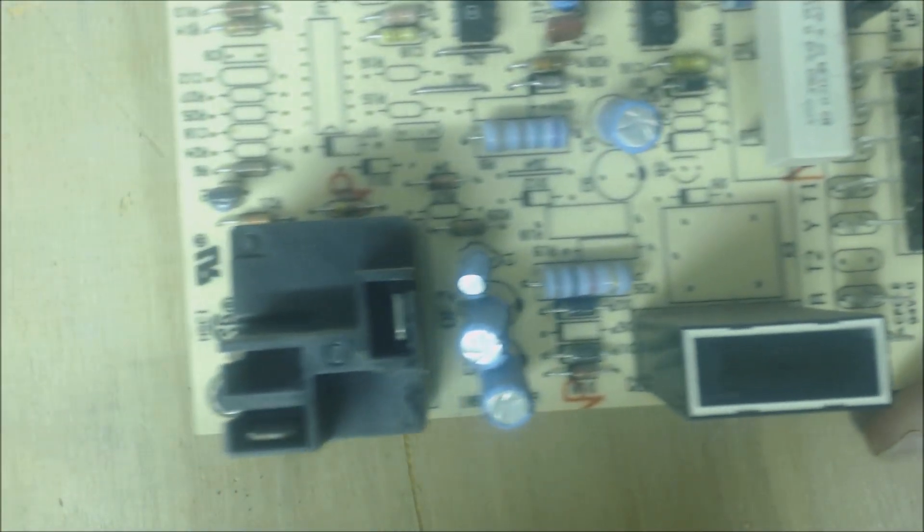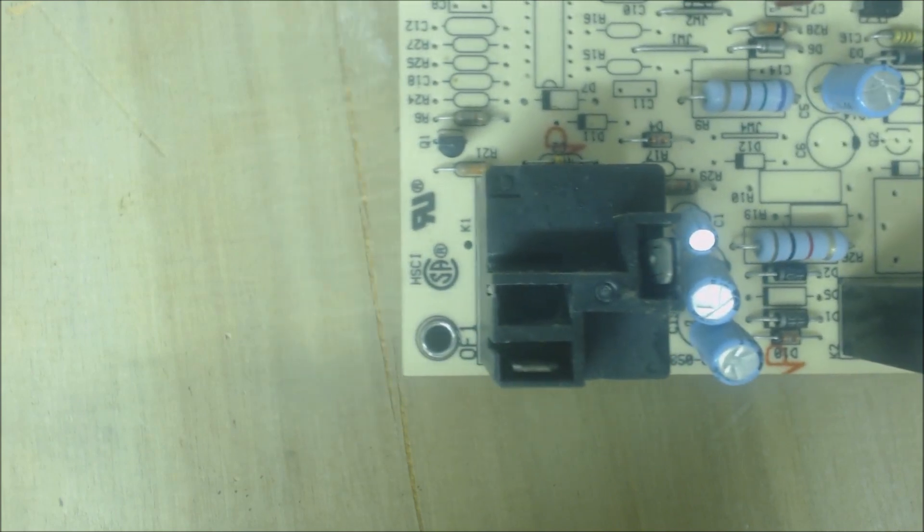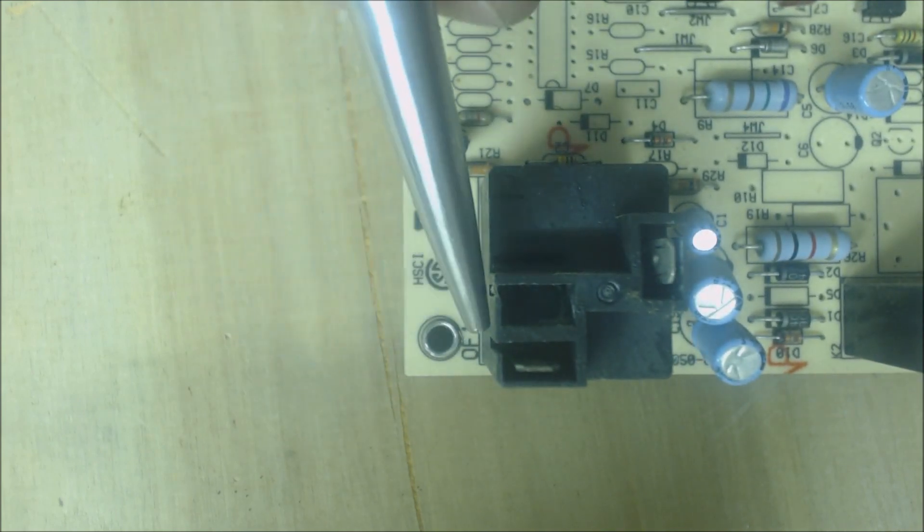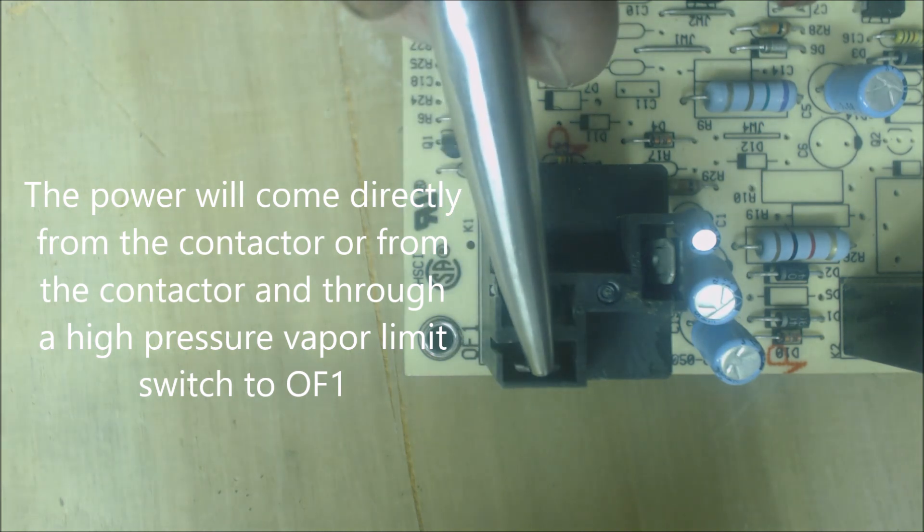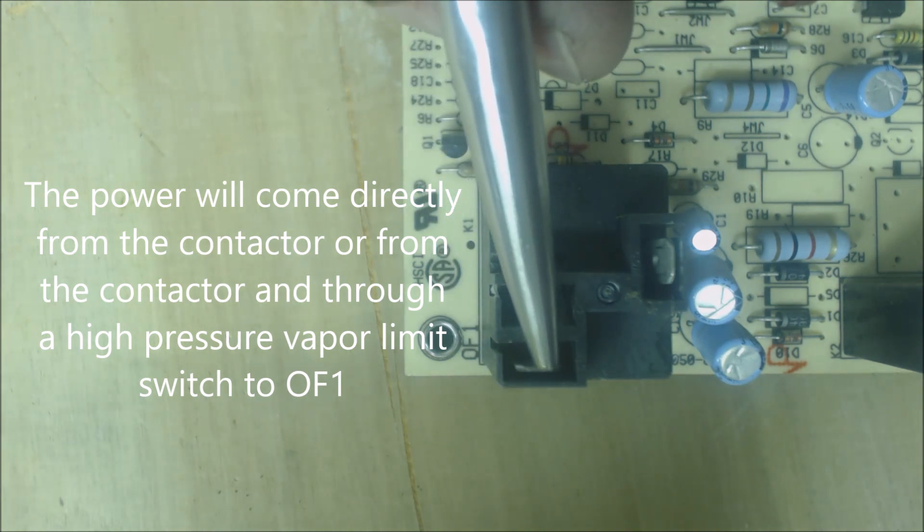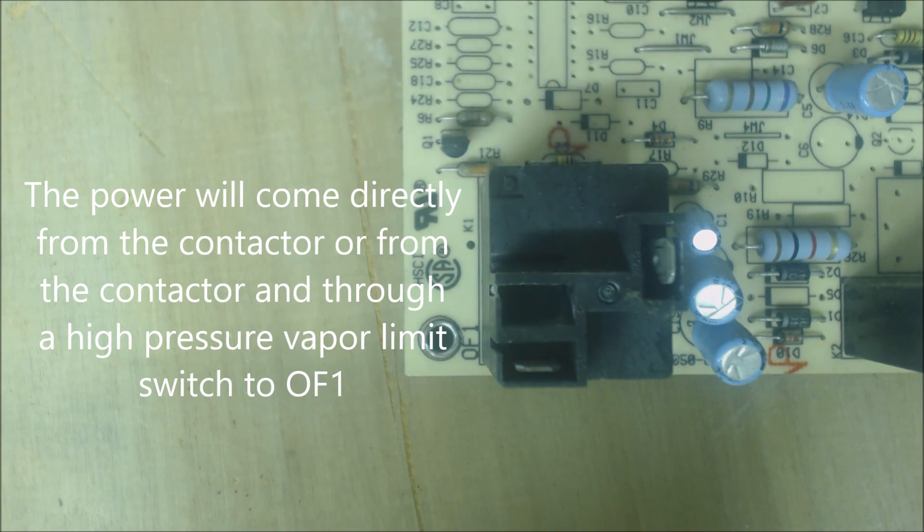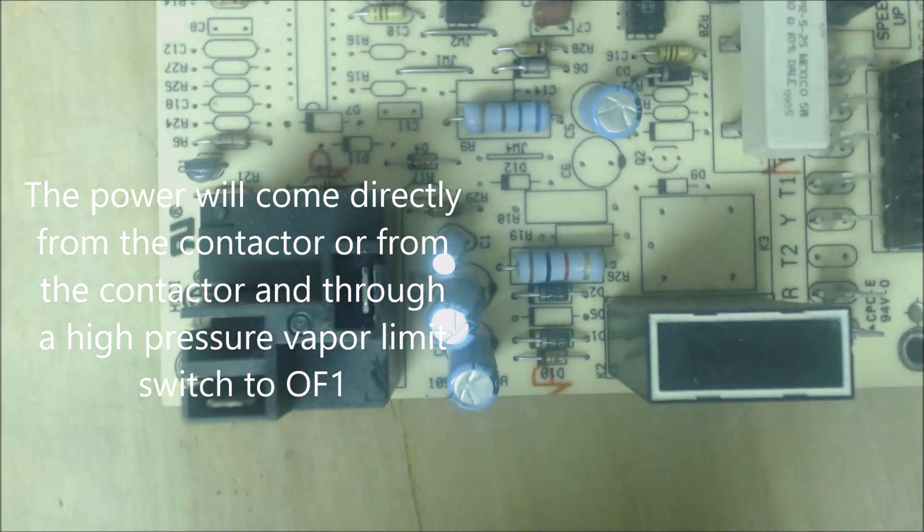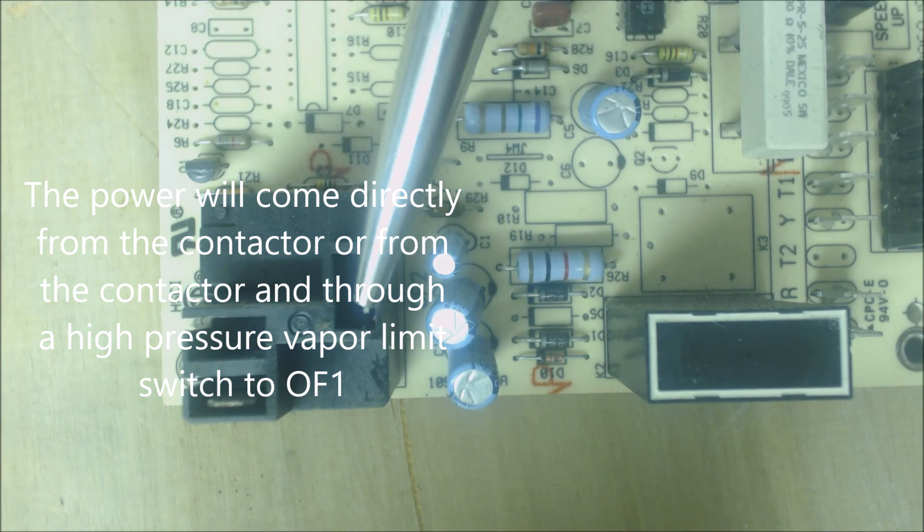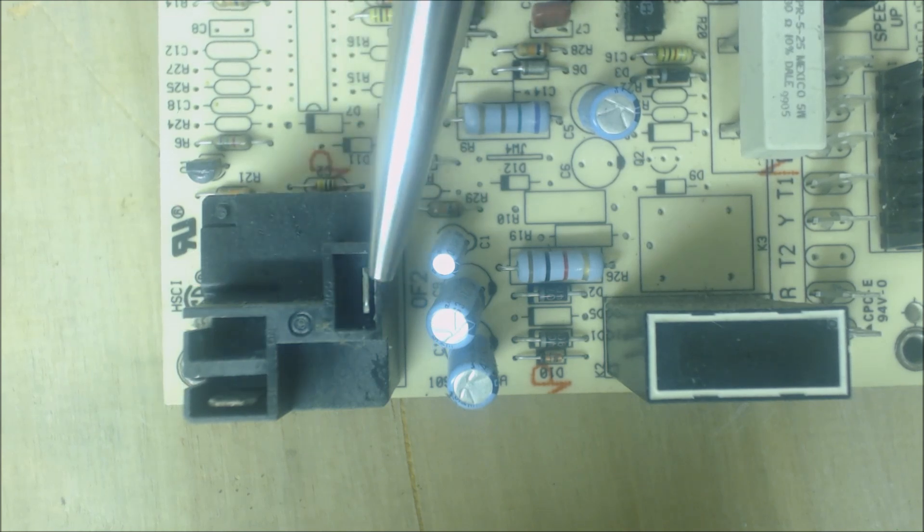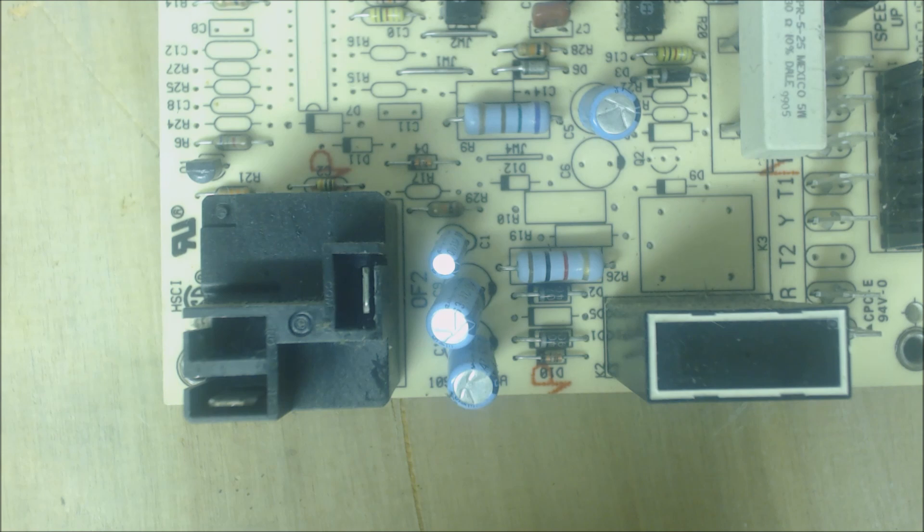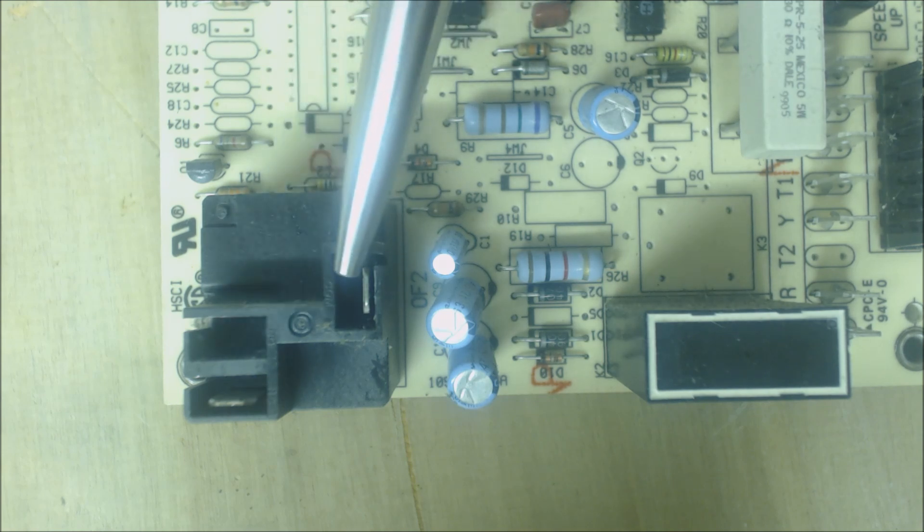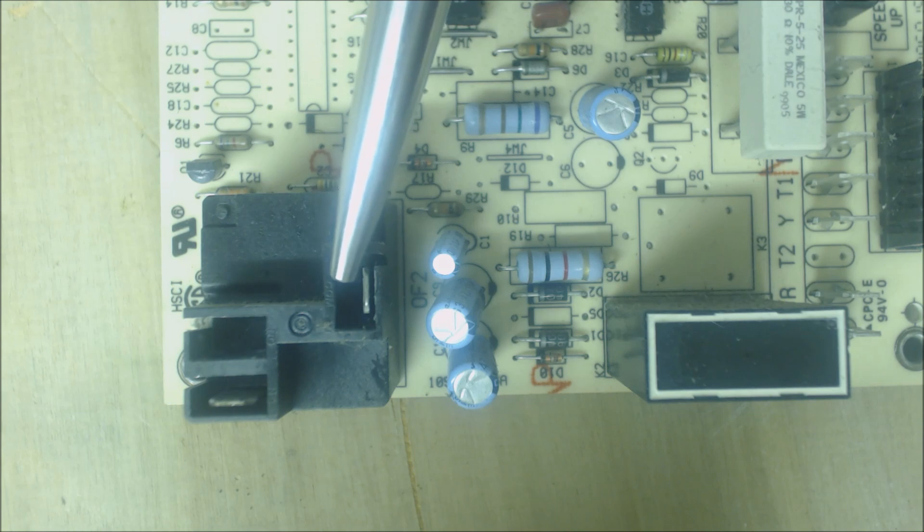One more thing happens during defrost. You have OF1 coming from the contactor—you have power coming from the contactor, it's 120 volt leg of the 240 volts—and then the relay can break that power as it comes off of OF2 and goes to the outdoor fan motor.